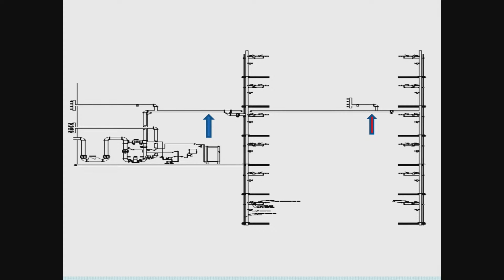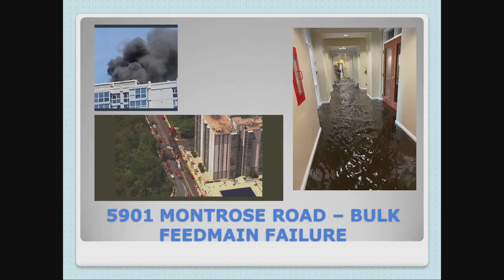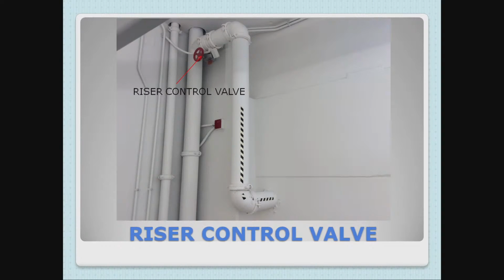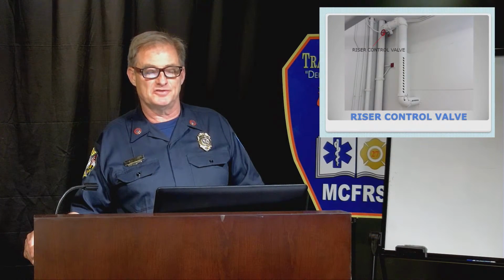But what I really want to talk about is what the potential workaround would be. So option A would be to try to isolate your standpipe from the break, and all of the standpipes should have what's called a riser control valve. That's represented by that valve just to the right of the arrow with the red in it. What we would do is, that's going to typically be found on a lower floor, first floor or maybe the first basement floor. It can be located in the stairs. It can be located just outside the stairs, but it should be pretty proximate to that riser that we want to control.